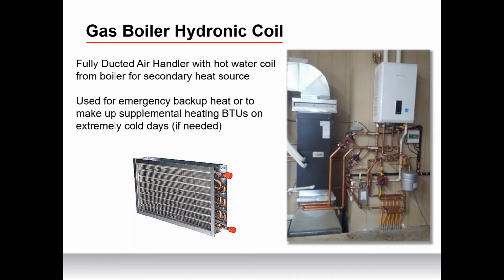So while we don't necessarily have the dual fuel product fully in-house right now, this is something that we can do any day. This picture that you're seeing right here is actually from a contractor in Southern Indiana that does this a lot. So he actually utilizes a single stage air source heat pump with this fully ducted solution, and then ties in this third-party hot water coil as second stage heat or backup heat. So this is an application we can do now, and it's growing in popularity as well.